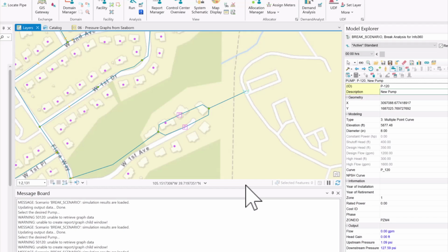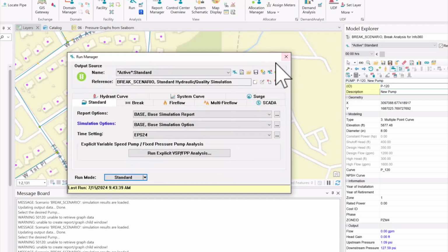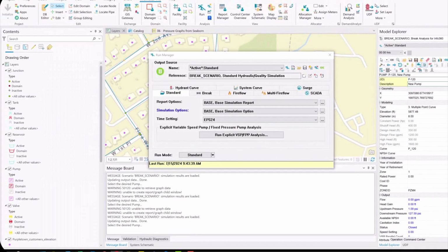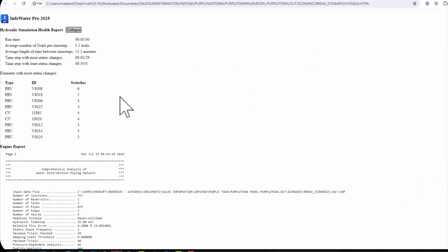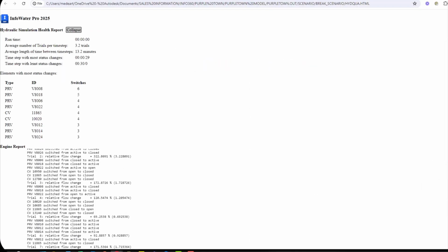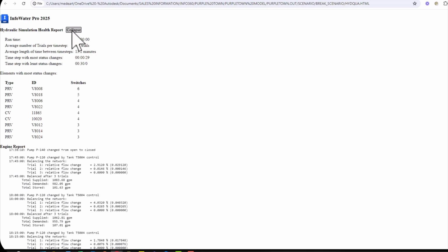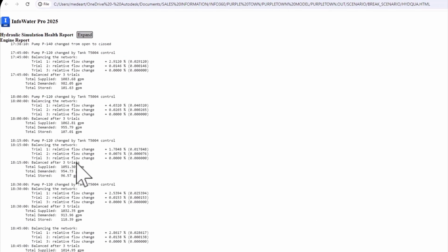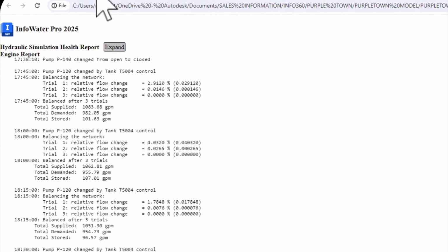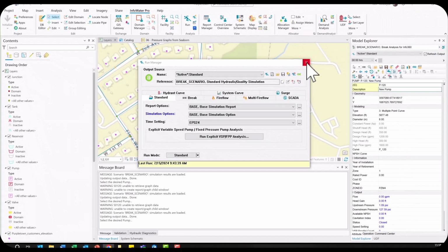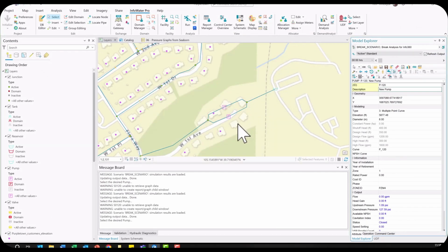thing we often see when we're looking at different hydraulic models, InfoWater Pro models, that within that EPANet engine, if you go to the actual hydraulic report here, if I were to have multiple variable speed pumps that were both on, they might be fighting each other and leading to instabilities here, and you would see this reflected in your hydraulic report as it'd be difficult potentially to balance out. So, those are just some guidelines for setting up variable speed pumps.